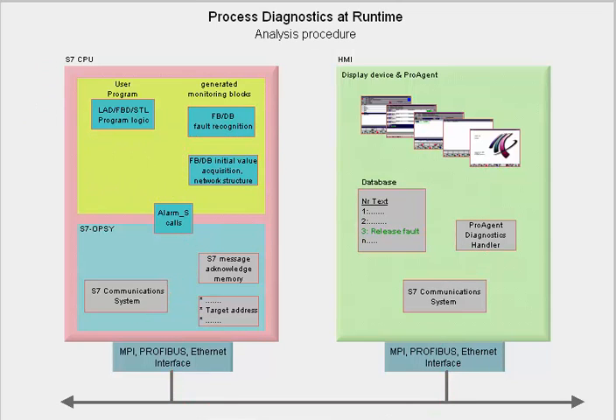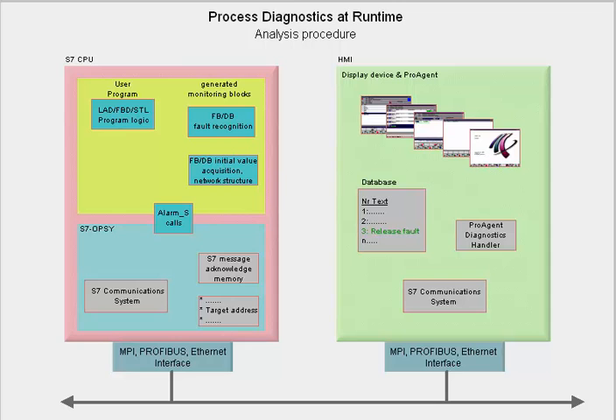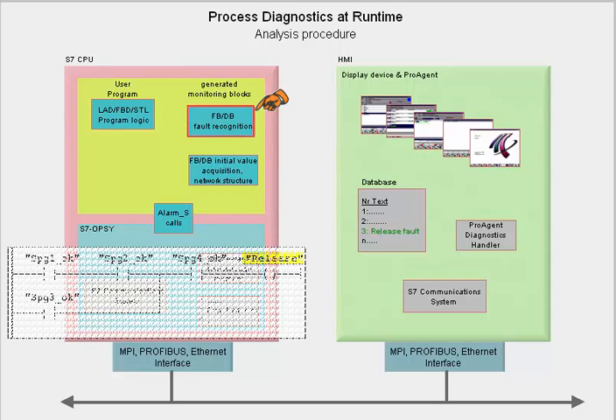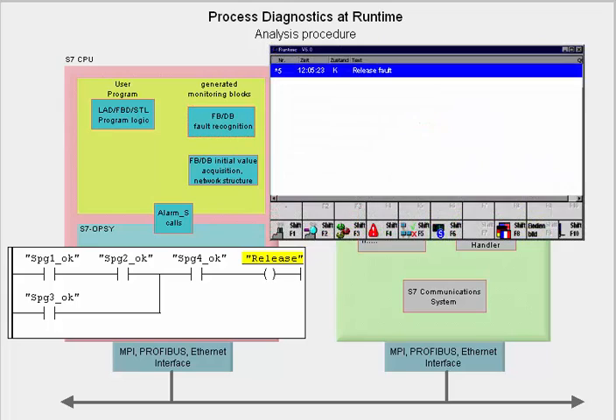Let us now turn to the analyzing process that makes it possible to determine the causes of a fault. We know that a fault has occurred in the process. However, what is important for fast troubleshooting is to locate the cause of the fault as precisely as possible. The monitoring block has recognized that the central release signal has left its set point state and has sent a message accordingly to the HMI device. But exactly which process signal is responsible can only be found out through criteria analysis.